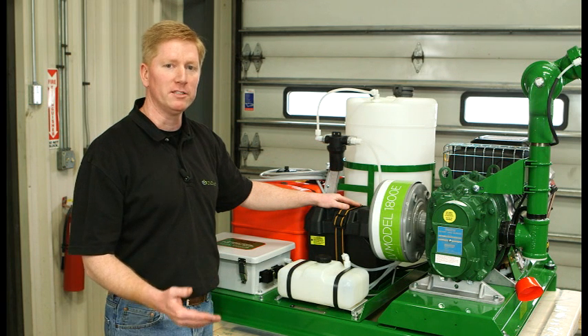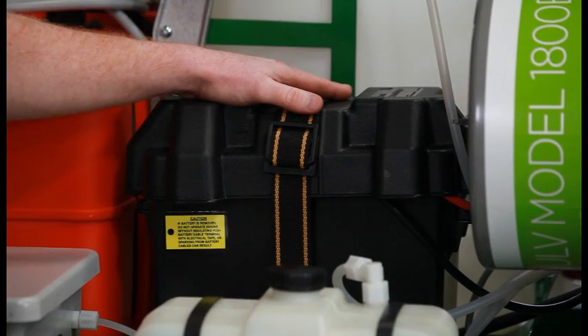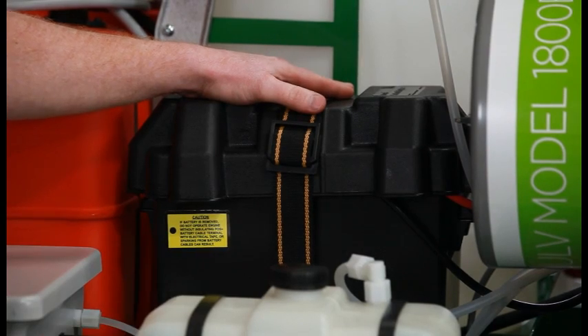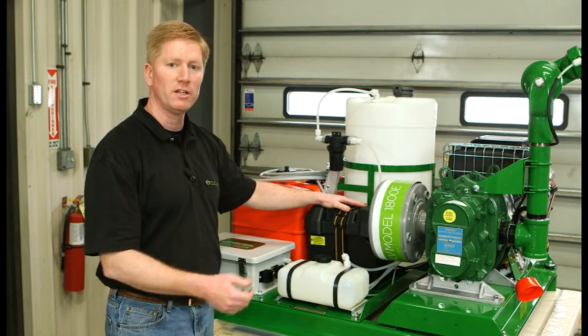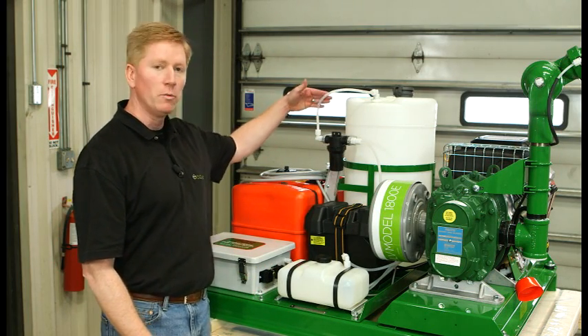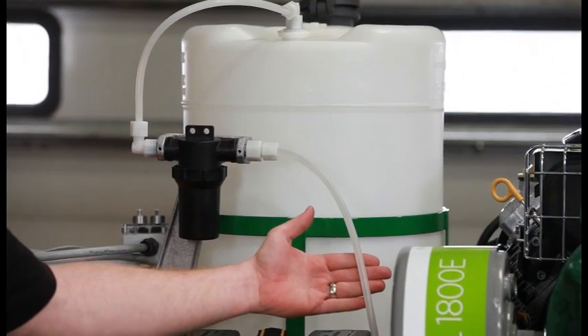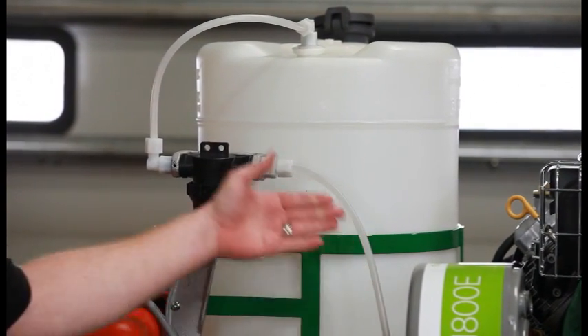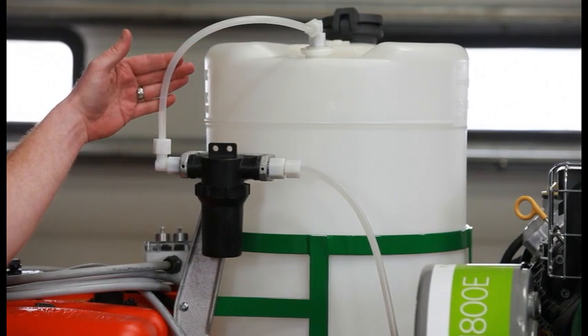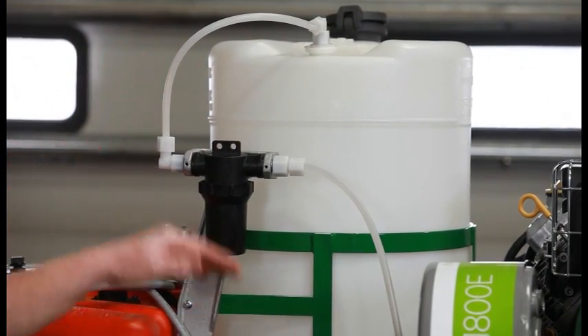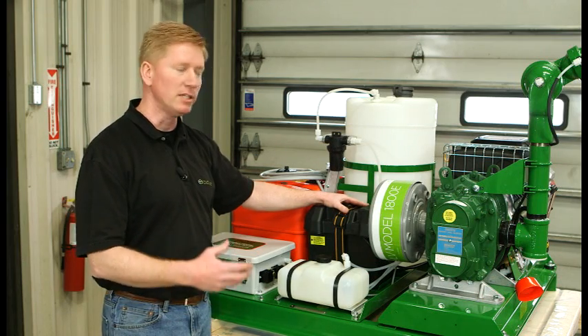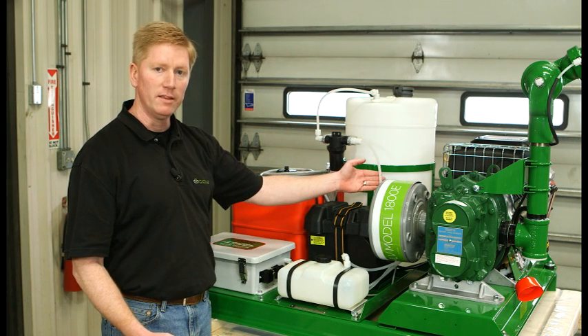Here's some additional maintenance for your machine. If you find any corrosion on your battery, use some baking soda and a wire brush to clean those connections. With your chemical lines, you can see that they're very clear and white. Once these lines start to discolor and turn yellow and brown, they become brittle, and it's time to replace these chemical lines.